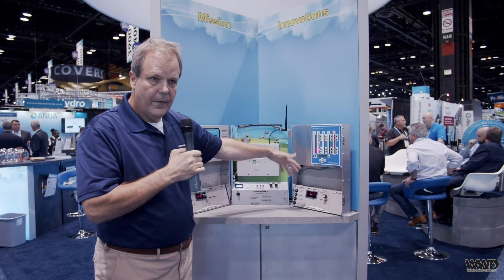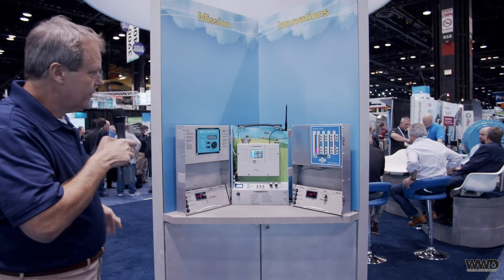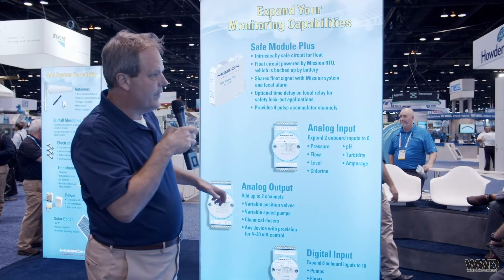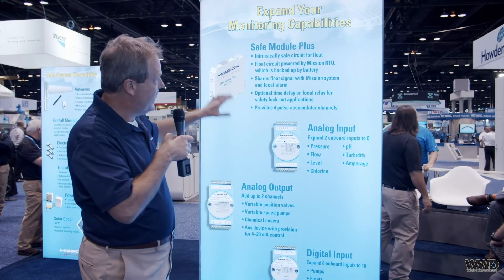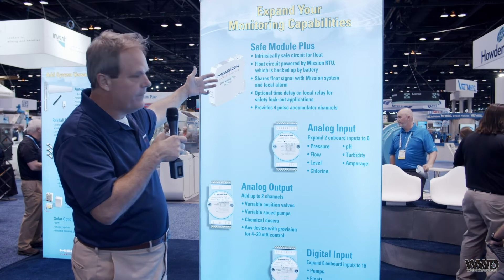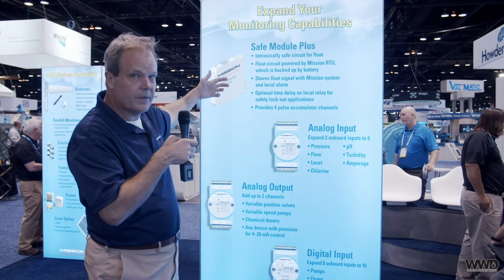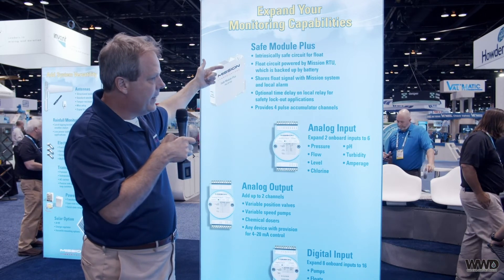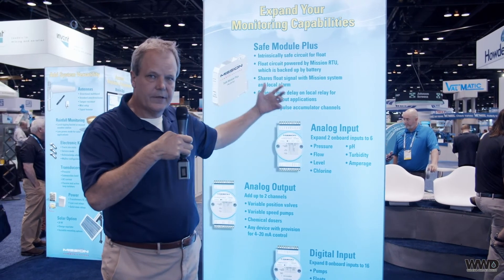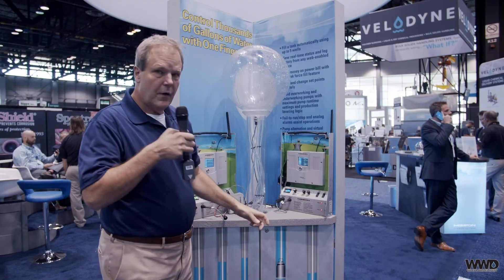We also now support the Multi-Trode Multi-Smart. Along with that, we're showing an additional expansion module. The Mission RTU has always supported expansion modules, but now we've added one that supports an intrinsically safe float input as well as Modbus connection to the RTU, pulse counting input, and an optional time-delayed interposing relay that facilitates installation of complicated lift stations and small water systems.